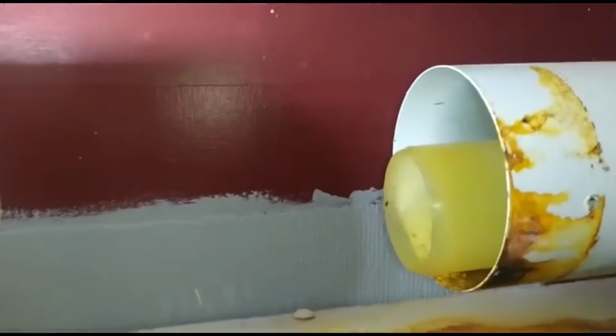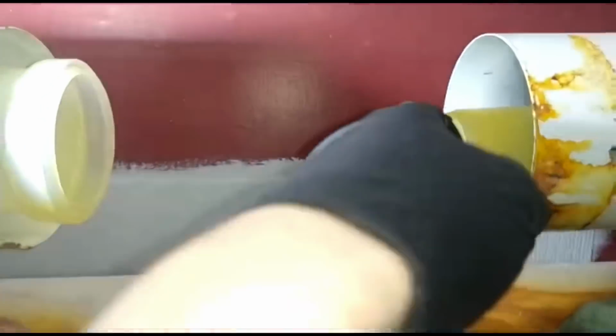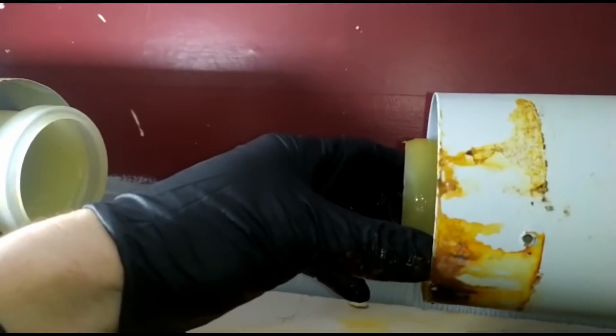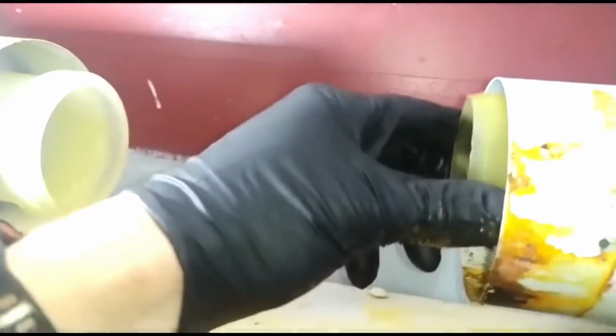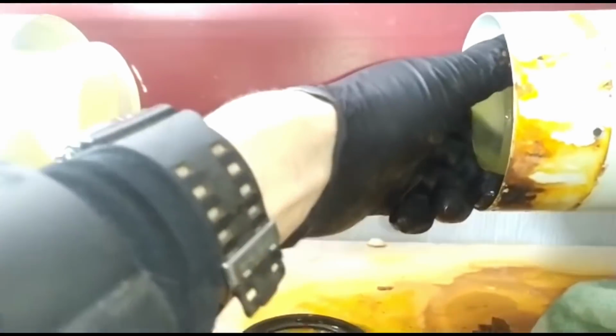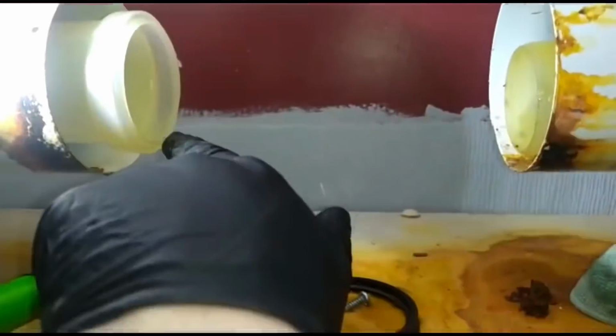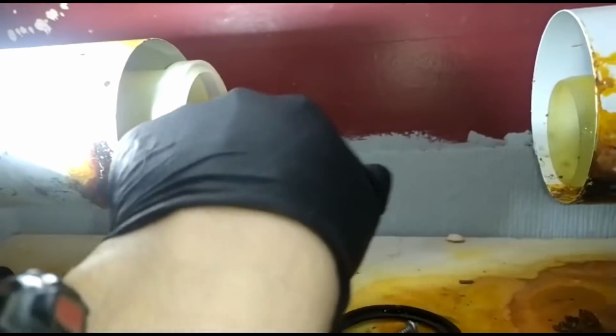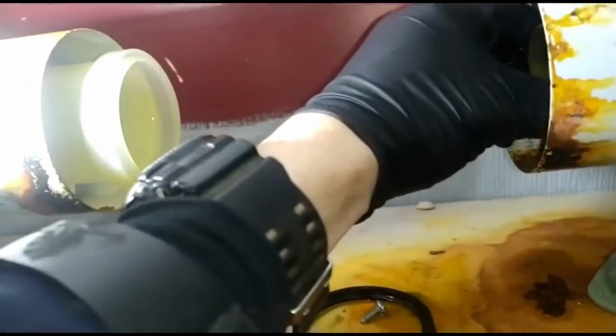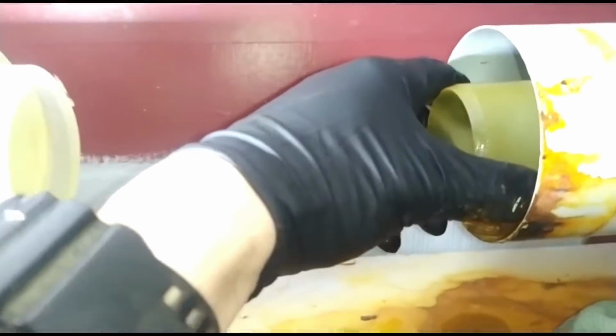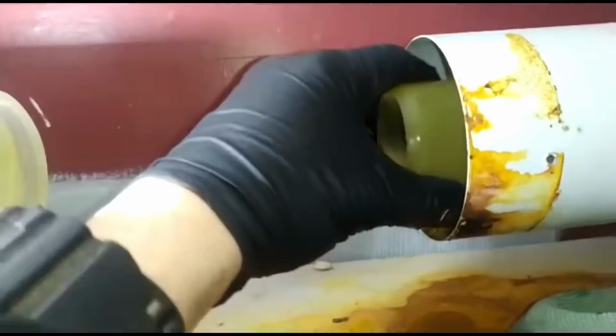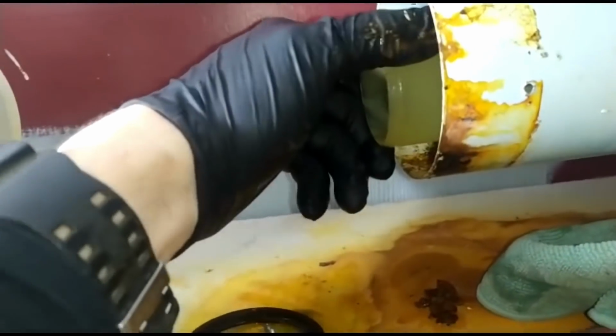Just a quick one, this is a Glow-worm, and the Vaillant flues are the same. There's a leak from the seal there. The inner core of the flue is meant to be longer than the outer core and fixed, you shouldn't be able to move it. When I took this apart, I found this flue wasn't all the way through engaging this O-ring here. You can see how you can move this flue quite a lot - you shouldn't be able to. They should lock into position, so you'll feel it lock, and that's it.